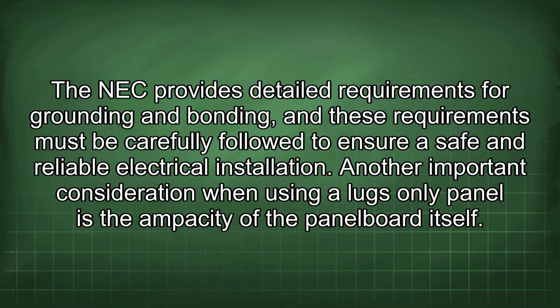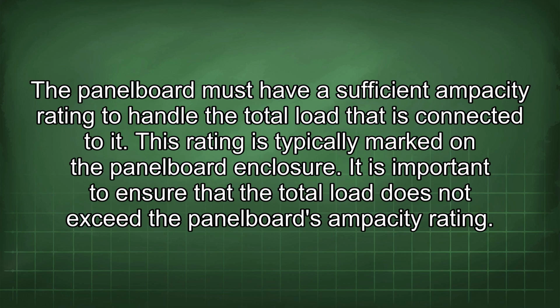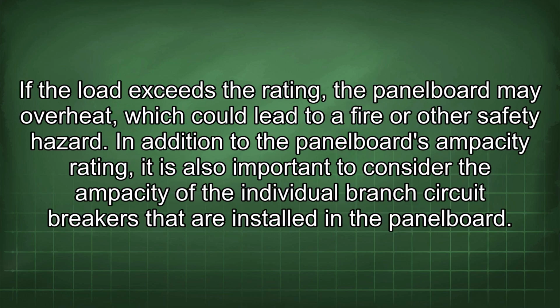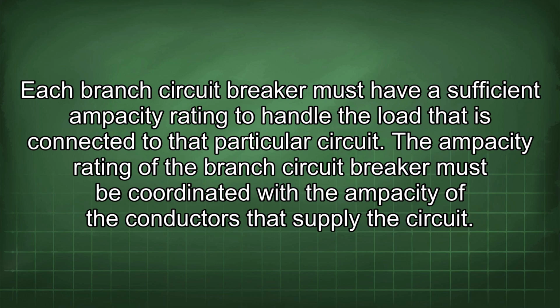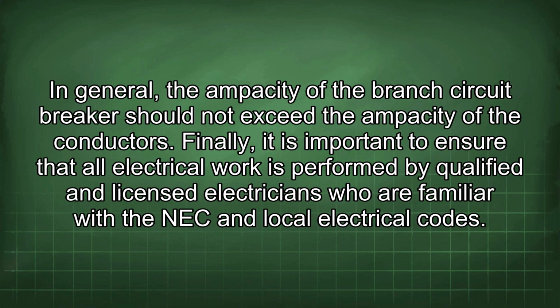Another important consideration when using a lugs-only panel is the ampacity of the panel board itself. The panel board must have a sufficient ampacity rating to handle the total load that is connected to it. This rating is typically marked on the panel board enclosure. It is important to ensure that the total load does not exceed the panel board's ampacity rating. If the load exceeds the rating, the panel board may overheat, which could lead to a fire or other safety hazard. In addition to the panel board's ampacity rating, it is also important to consider the ampacity of the individual branch circuit breakers that are installed in a panel board. Each branch circuit breaker must have a sufficient ampacity rating to handle the load that is connected to that particular circuit. The ampacity rating of the branch circuit breaker must be coordinated with the ampacity of the conductors that supply the circuit. In general, the ampacity of the branch circuit breaker should not exceed the ampacity of the conductors.